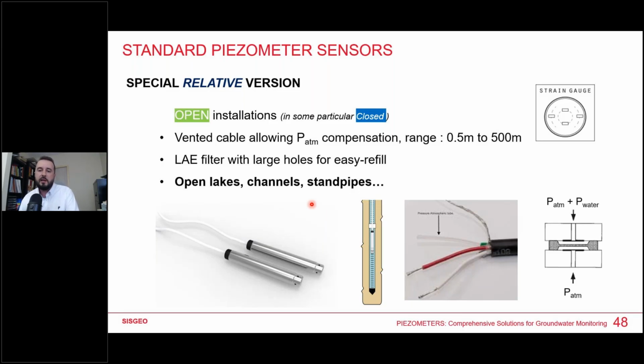So the relative version is mainly used in open installations, so in lakes, in channels, in standpipes. For that, we use compensating tubes. So inside the cable, inside the main body, it's not only an electric cable, but you will find a small tube which is linking the surface, so the atmosphere, and the main body. So the body inside the sensor is no more blocked and no more sealed from its pressure. So then you will compensate mainly the atmospheric pressure. You have the same atmospheric pressure in front of the diaphragm and behind the diaphragm. So this value is compensated. So it's good with this sensor because you don't need any barometric measurement on the site.